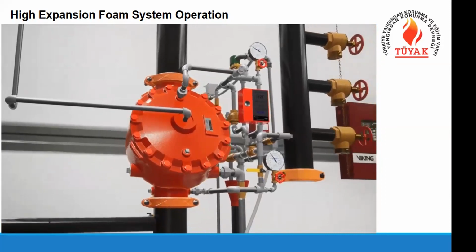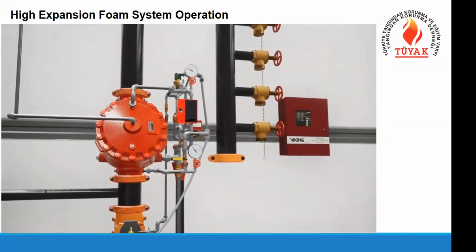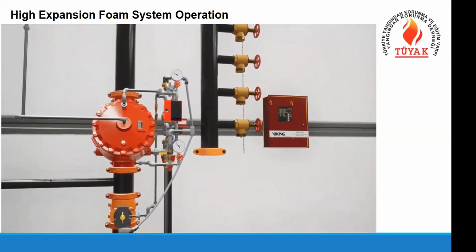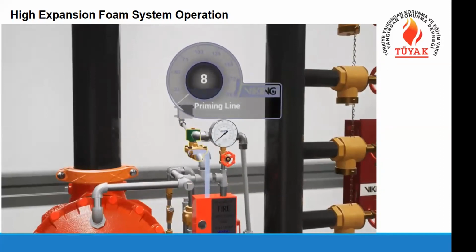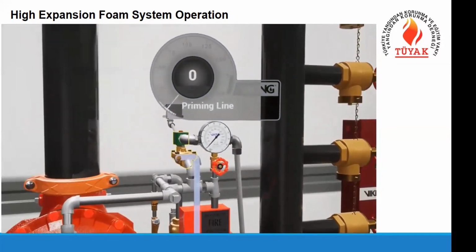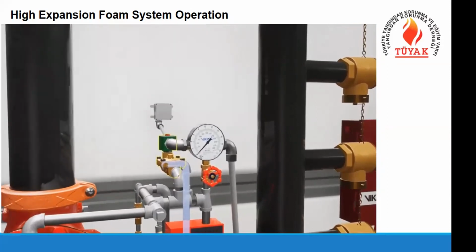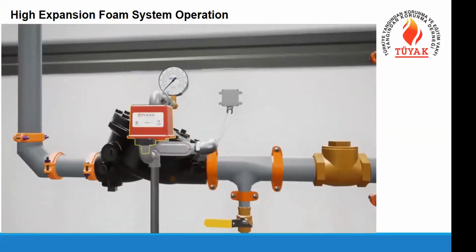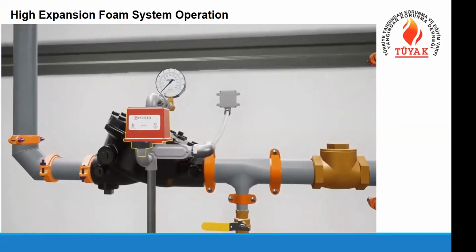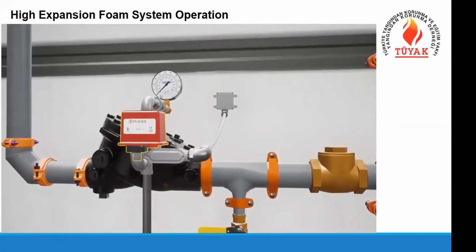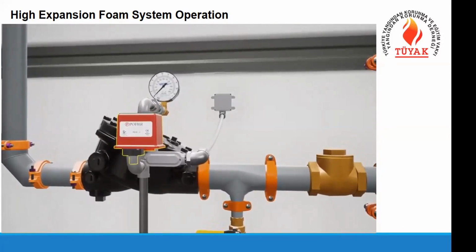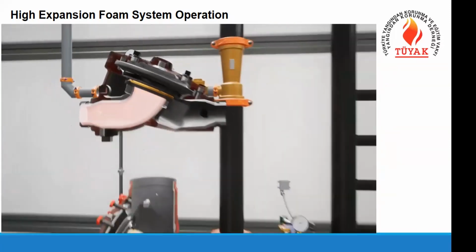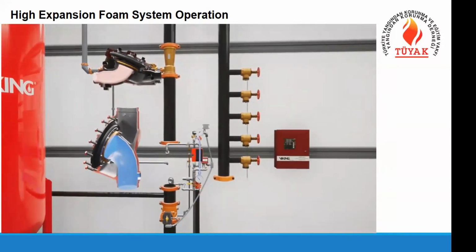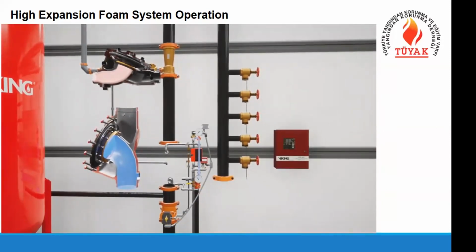In a scenario where a fire has started in the hangar and begins to grow, the electric detection device activates and sends a signal to the VFR 400 release control panel. The electric solenoid valve is powered open, releasing water pressure within the priming chambers of the deluge valve and the concentrate control valve. The drop of prime pressure causes the priming line pressure switch to activate. Priming line pressure switches are required for Factory Mutual global approval. After the release of prime pressure, the deluge valve's clapper and the concentrate control valve's clapper open simultaneously.